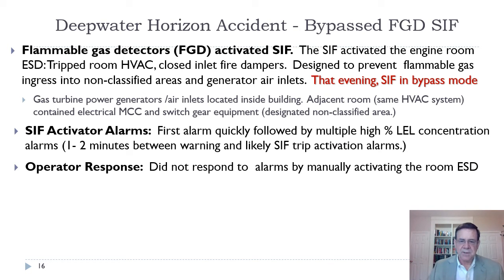But the evening of the accident, for the person on duty, from the first pre-alarm that came in on gas to the point where you had met the gas activation trip point, and now have all kinds of gas alarms activated, was less than 1 to 2 minutes. In the process of this short time, the person never activated the ESD, and it's not clear that this person knew that several minutes prior the drill shack had realized that a kick was in progress and a gas release was possible.